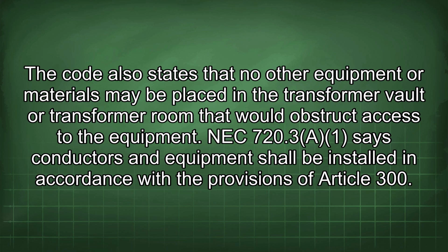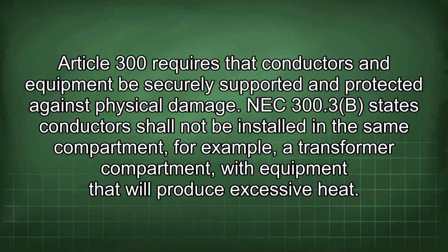NEC 720.3a says conductors and equipment shall be installed in accordance with the provisions of Article 300. Article 300 requires that conductors and equipment be securely supported and protected against physical damage.